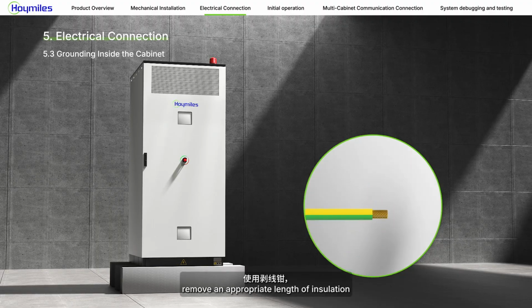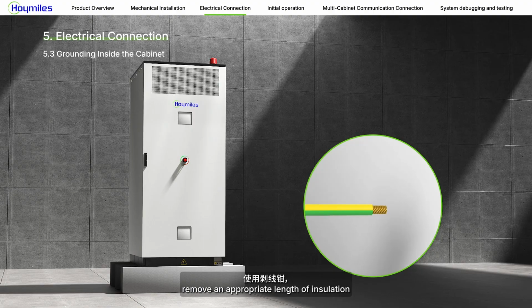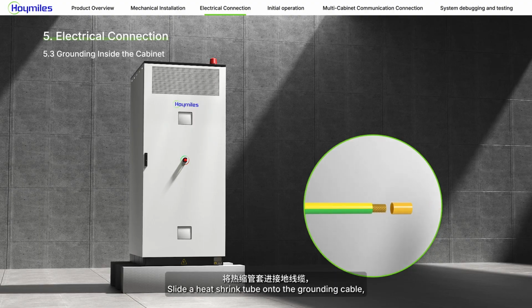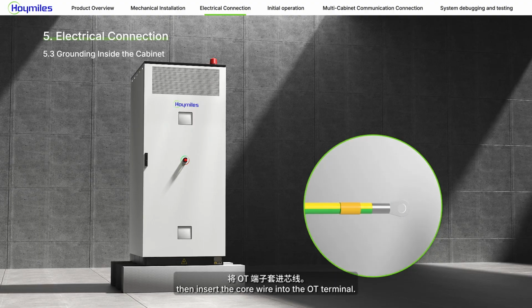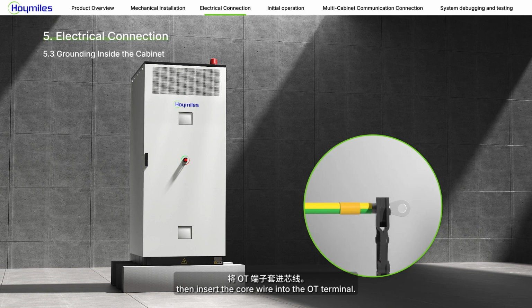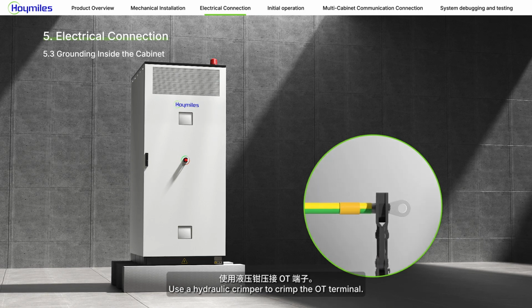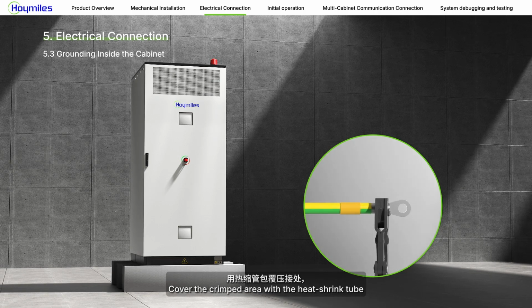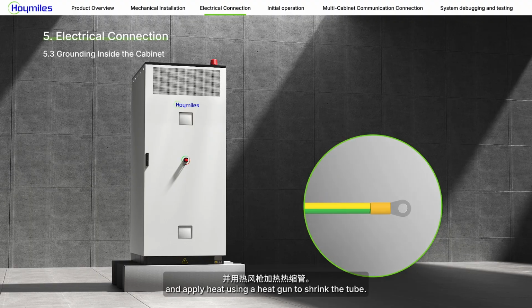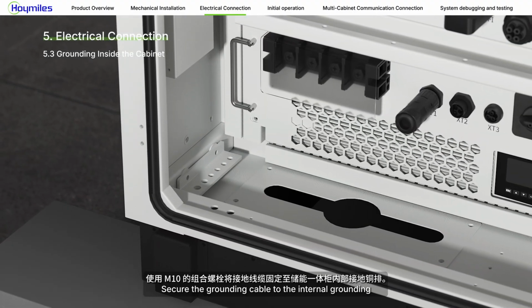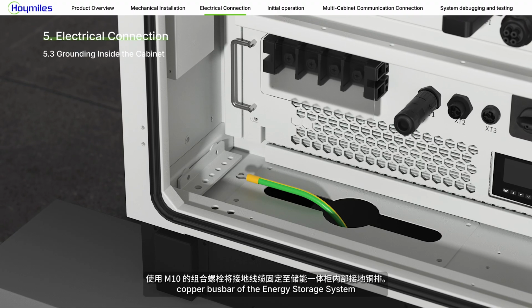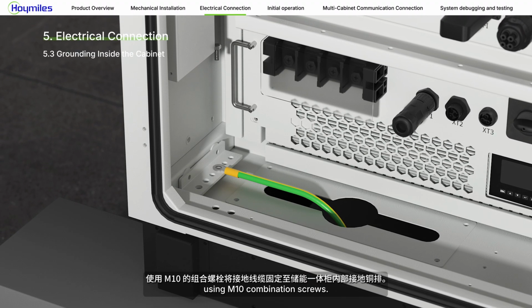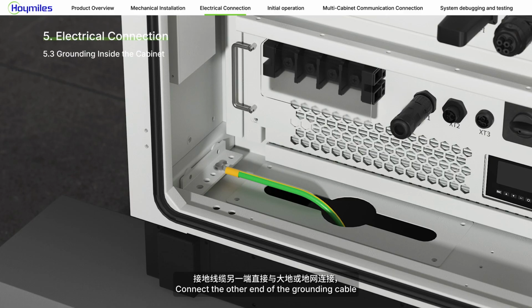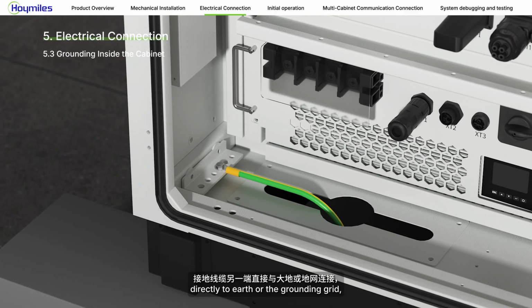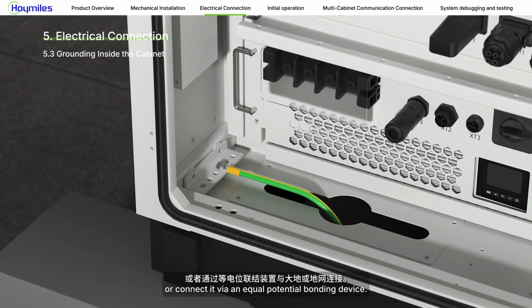Use a wire stripper to remove an appropriate length of insulation from the cable. Slide a heat shrink tube onto the grounding cable, then insert the core wire into the OT terminal. Use a hydraulic crimper to crimp the OT terminal. Cover the crimped area with the heat shrink tube and apply heat using a heat gun to shrink the tube. Secure the grounding cable to the internal grounding copper busbar of the energy storage system using M10 combination screws.